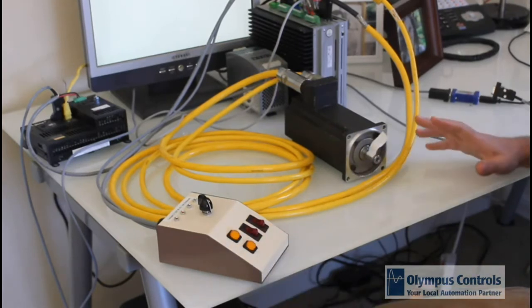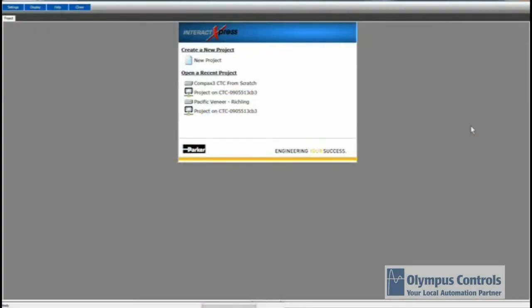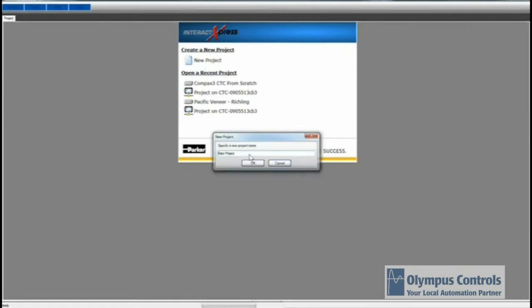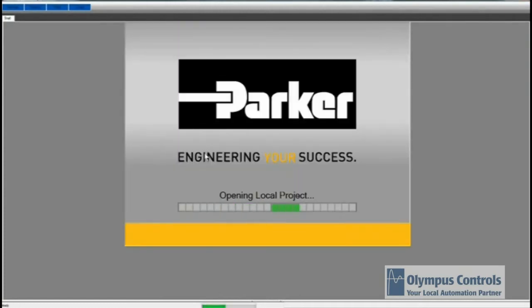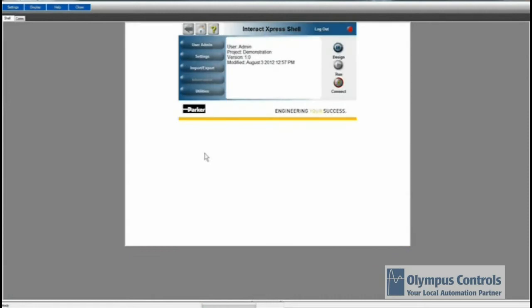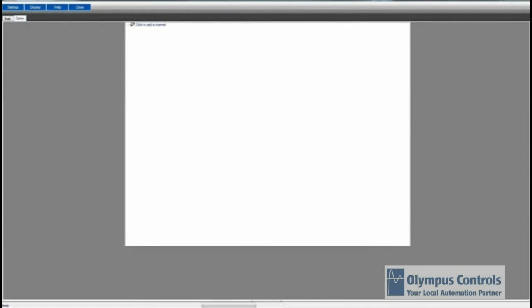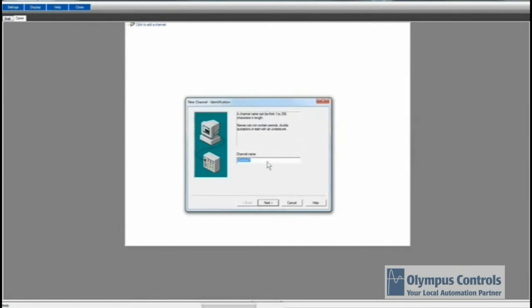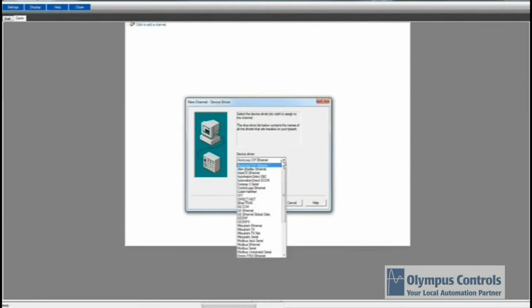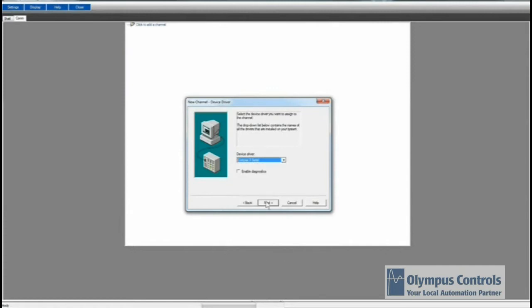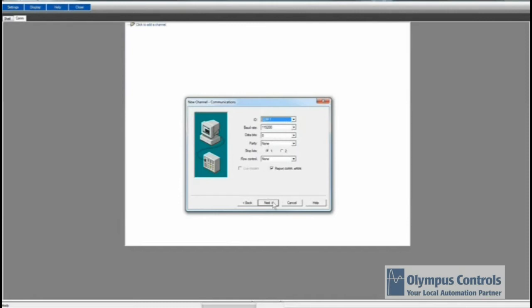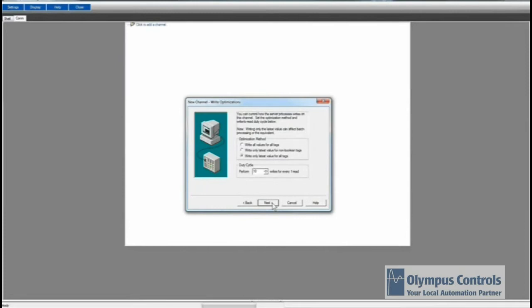Next, we'll make that happen using Interact Express. What we have here is Interact Express opened from the beginning, and we're going to start from a new project. So we click New Project. We'll call this Demonstration. From here, we want to go to the Com panel up here in the top left. We go to Add New Channel. Channel name, we'll call C3. We're going to make it a Compax3 serial. We'll go to Next. Com1, we'll use all the defaults here. We're going to hook it up to Com1. And all the defaults all the way through.